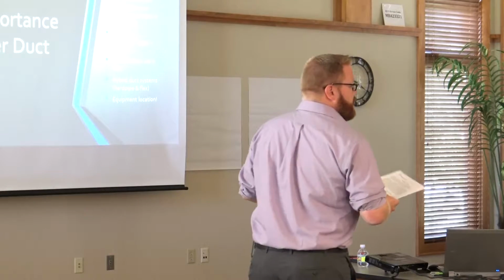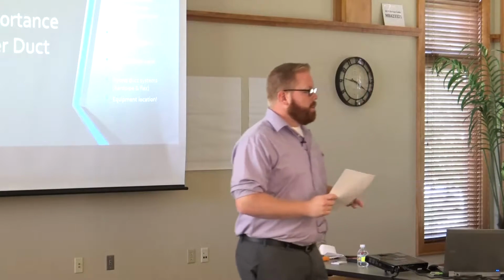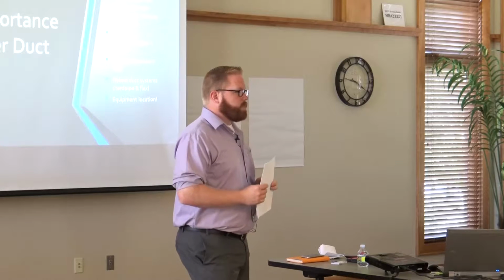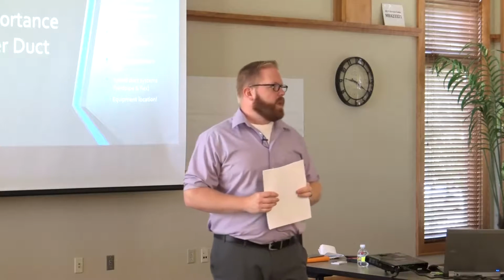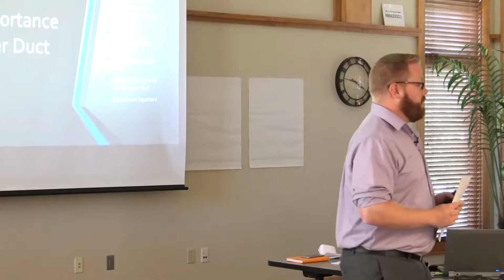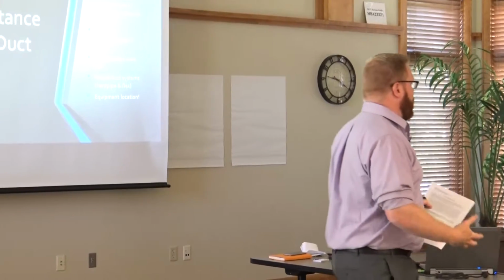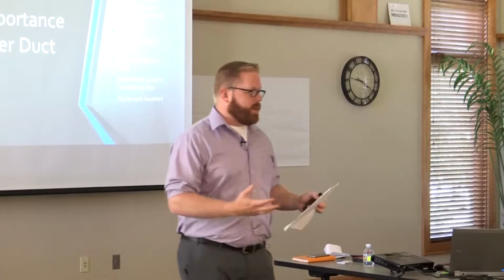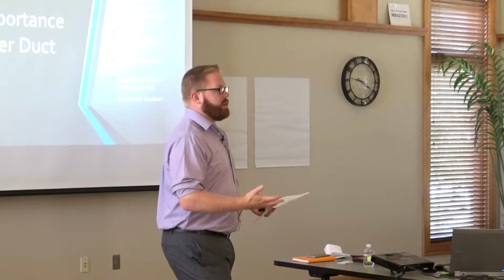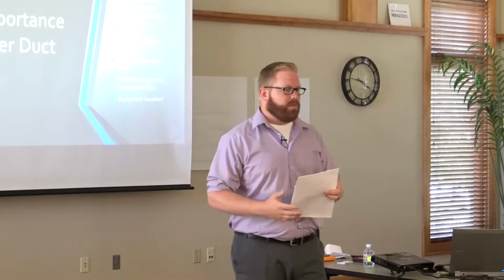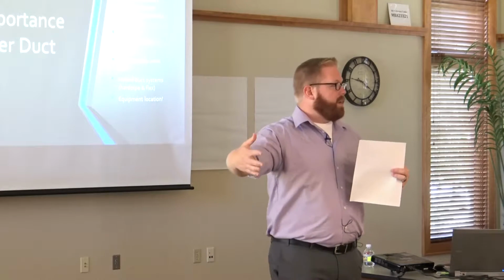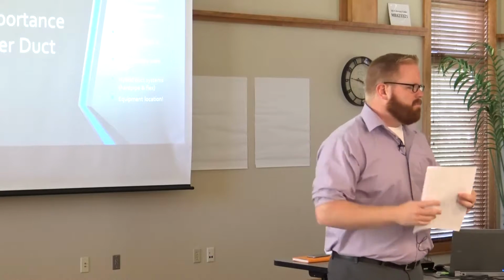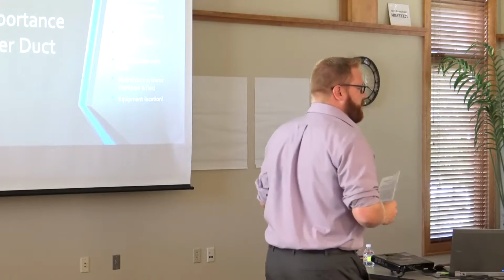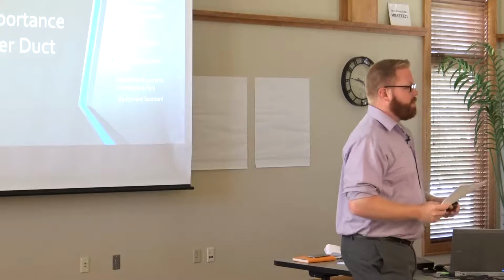So obviously, oops, sorry, go ahead. The reason for that is that the air isn't getting through that flex like it should? Correct. Exactly. Flexible ductwork, if installed properly, actually has a really good place in the industry. If it's not over a great length of ductwork, and it's installed properly, flexible ductwork, again, can actually perform pretty well.